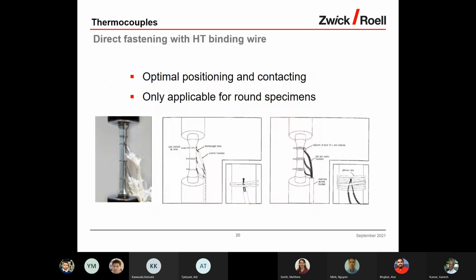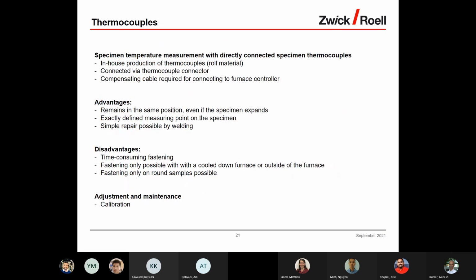Direct fastening with a high temperature binding wire: optimal positioning and contacting, and only applicable for round specimens. This is the picture on the left. You need a lot of patience when binding the thermocouples to the sample. Specimen temperature measurement with directly connected specimen thermocouples.